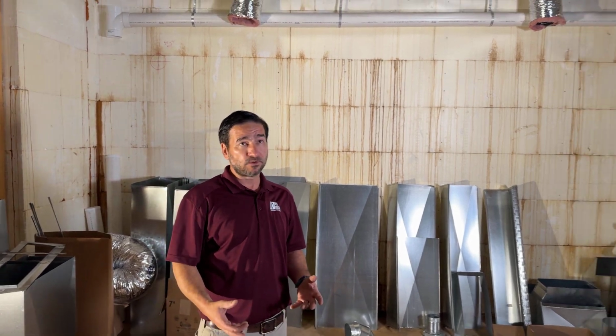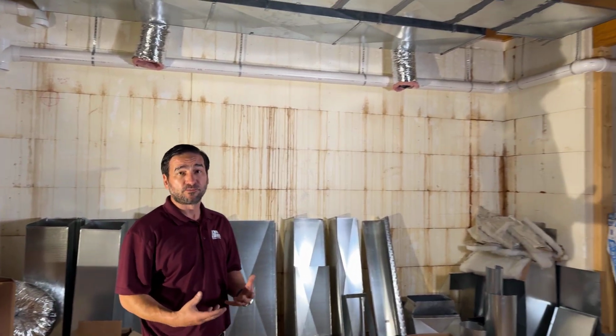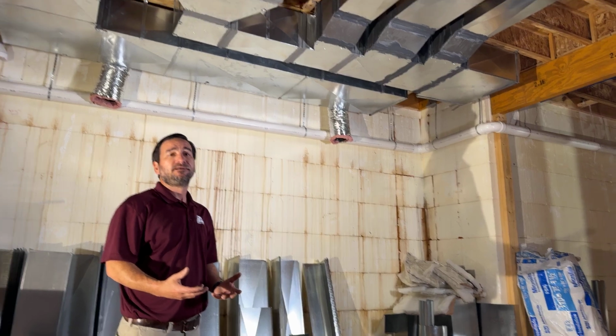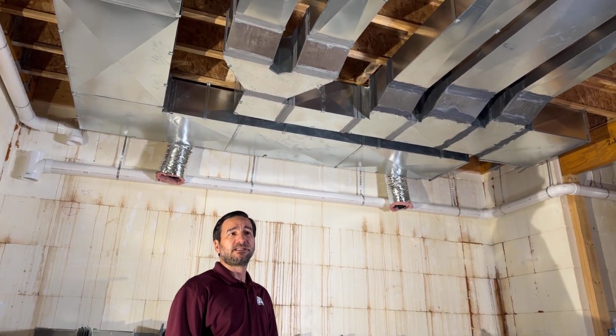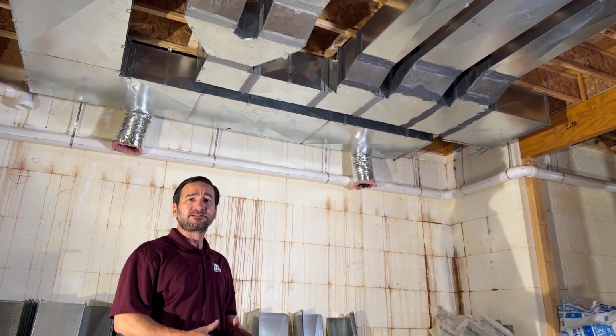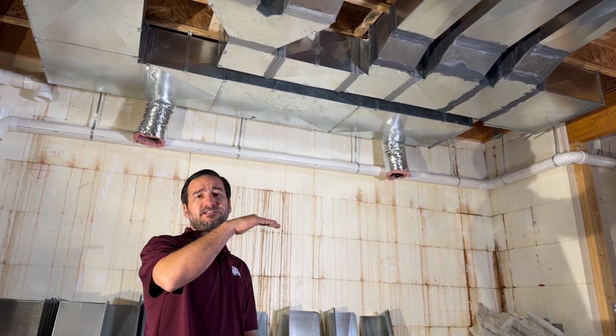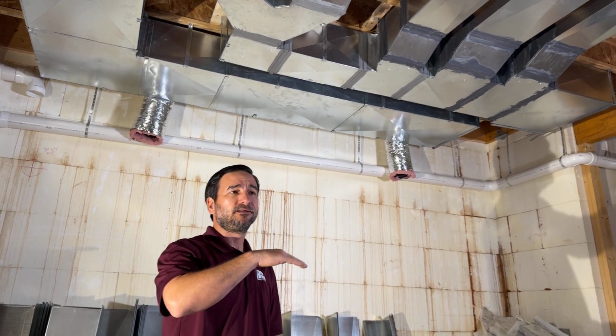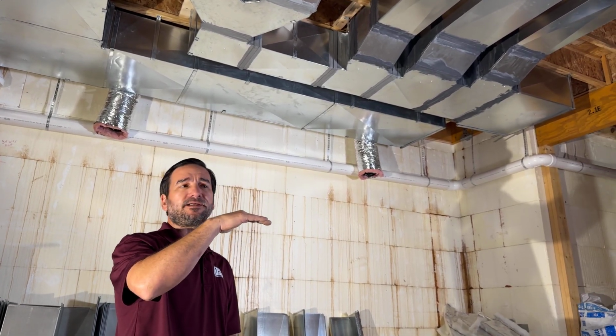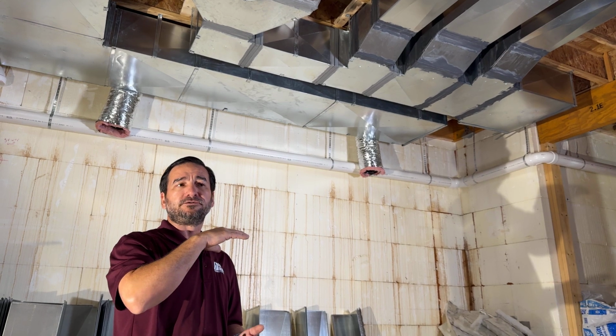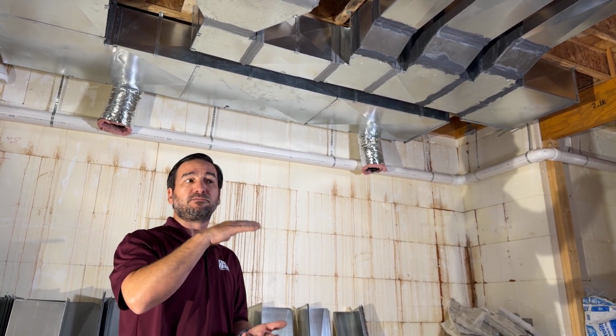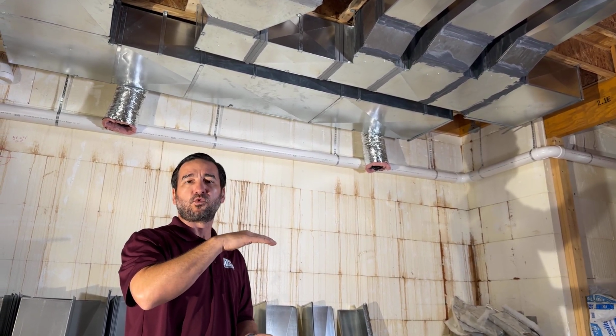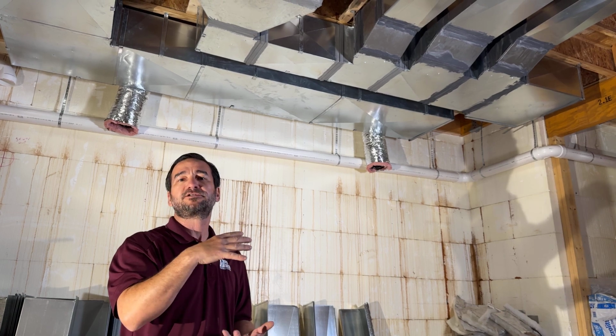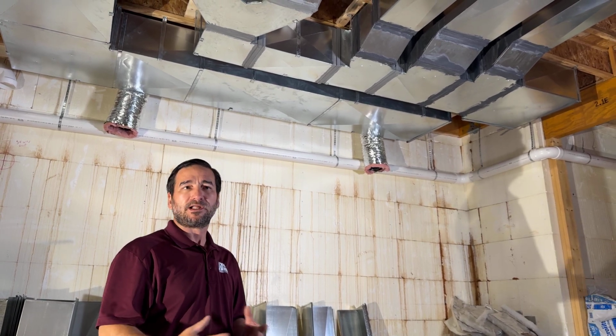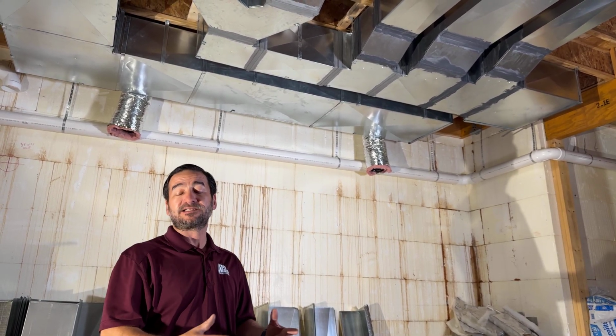The most elegant way to do zoning is to use multi-stage HVAC equipment. The better zone controls will allow you to give the zones a weight. So you could say the first floor is 50% of the zone weight, the second floor is 50% of the zone weight, and then you could tell the control, don't go into high blower speed unless you have more than 50% of the zones calling. So that's a much more elegant way to control the capacity of a system.